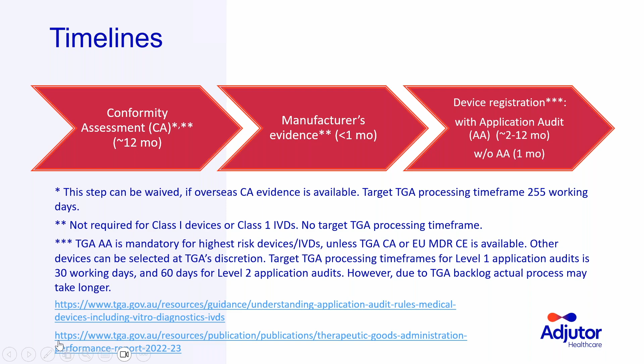This step usually takes around 1 month and is administrative in nature, unless the product is selected for a TGA application audit. Now, some devices must undergo a mandatory TGA audit. For example, the highest risk class 3 devices or class 4 IVDs, but also IVDs for self-testing. Any other medical device can be selected, however, at the TGA's discretion. If selected, the TGA reviews the technical documentation and also any conformity assessment evidence. They do have target processing timeframes, which can be between 30 and 60 days, depending on the level of the review. 60 days, of course, stands for the more in-depth audit. Unfortunately, though, due to TGA backlogs, the actual process may take much longer. And in our experience, this step can take up to 1 year, which is, of course, the worst case scenario.